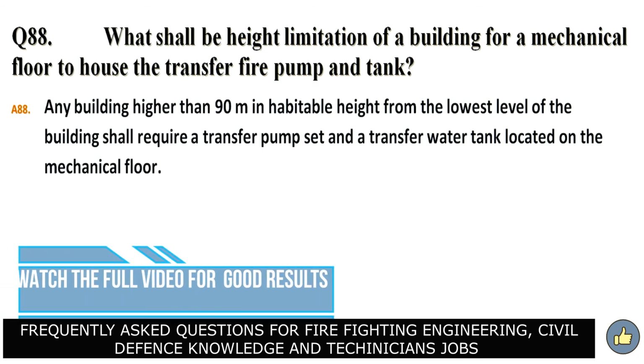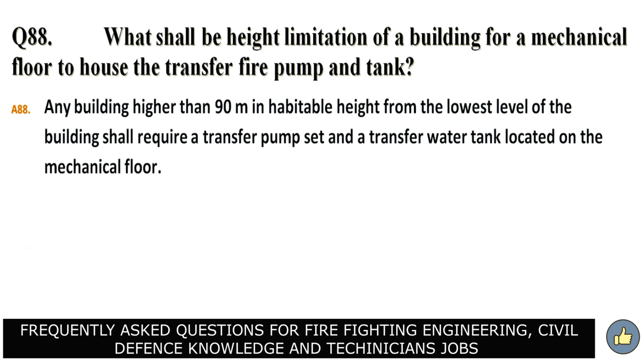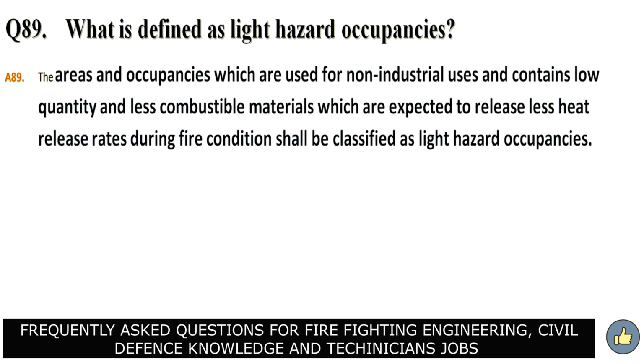Any building higher than 90 meter in habitable height from the lowest level of the building shall require a transfer pump set and a transfer water tank located on the mechanical floor. What is defined as light hazard occupancies? Answer. The areas and occupancies which are used for non-industrial uses and contains low quantity and less combustible materials which are expected to release less heat release rates during fire conditions shall be classified as light hazard occupancies.